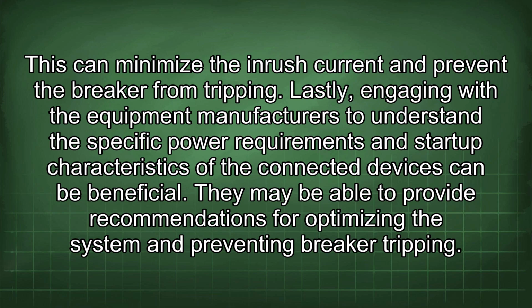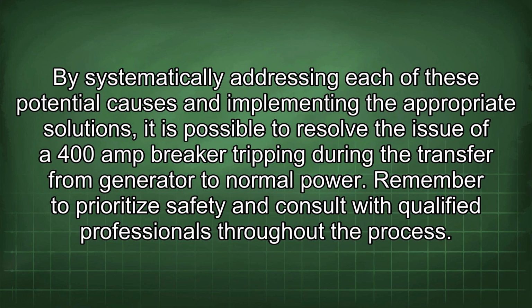Lastly, engaging with the equipment manufacturers to understand the specific power requirements and startup characteristics of the connected devices can be beneficial. They may be able to provide recommendations for optimizing the system and preventing breaker tripping. By systematically addressing each of these potential causes and implementing the appropriate solutions, it is possible to resolve the issue of a 400 amp breaker tripping during the transfer from generator to normal power. Remember to prioritize safety and consult with qualified professionals throughout the process.